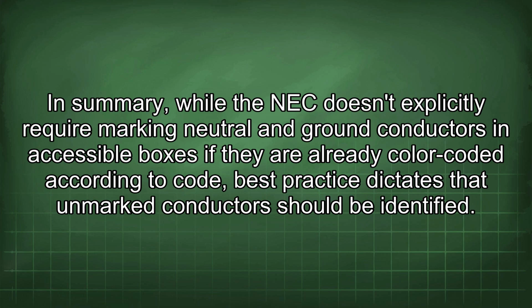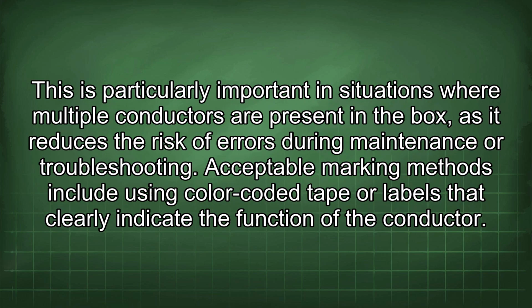In summary, while the NEC doesn't explicitly require marking neutral and ground conductors in accessible boxes if they are already color-coded according to code, best practice dictates that unmarked conductors should be identified. This is particularly important in situations where multiple conductors are present in the box, as it reduces the risk of errors during maintenance or troubleshooting. Acceptable marking methods include using color-coded tape or labels that clearly indicate the function of the conductor.